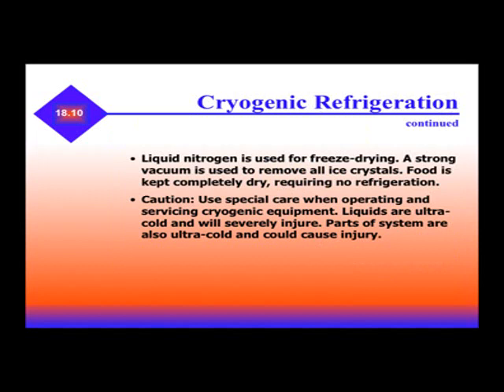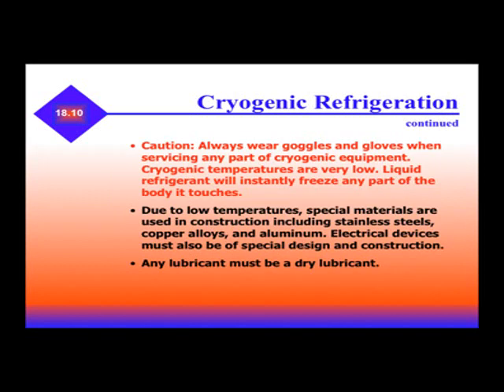A strong vacuum is used to remove all ice crystals in freeze drying, and food is kept completely dry, requiring no refrigeration. When using cryogenic equipment, be careful — you need to use special care when operating and servicing. Liquids are ultra-cold and will severely injure you, and parts of the system are also ultra-cold and could cause injury. Always wear goggles and gloves when servicing any part of cryogenic equipment. Liquid refrigerant will instantly freeze any part of the body it touches. Due to low temperatures, special materials are used in construction, including stainless steel, copper alloys, and aluminum. Electrical devices must be of special design to handle the cold temperatures, and any lubricant used must be a dry lubricant.